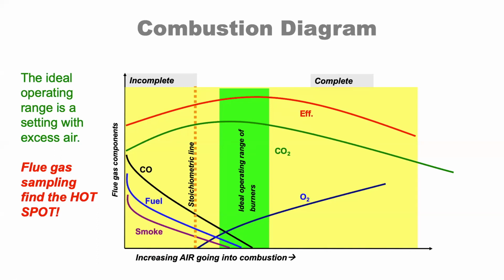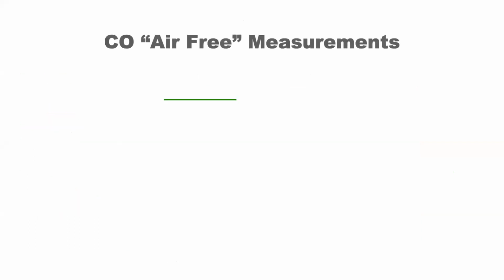You want to make sure that, because flue gas does change composition even across the stack, even across the exhaust tube that you're measuring it in. So you want to use flue gas sampling by looking for the hottest spot to find the correct place to make your measurement. That's something you can do with the analyzers: watching the temperature until it reaches the peak. That's when you want to snapshot the combustion gas measurements.